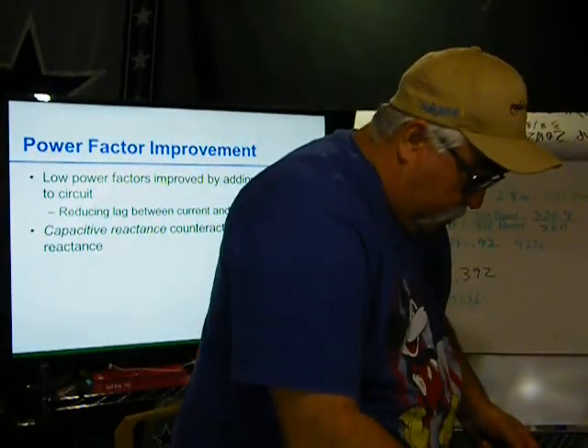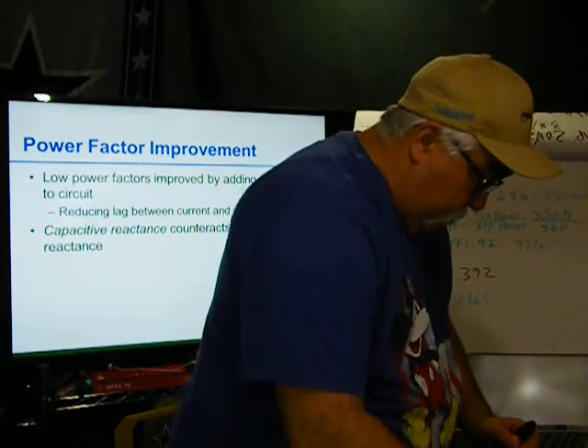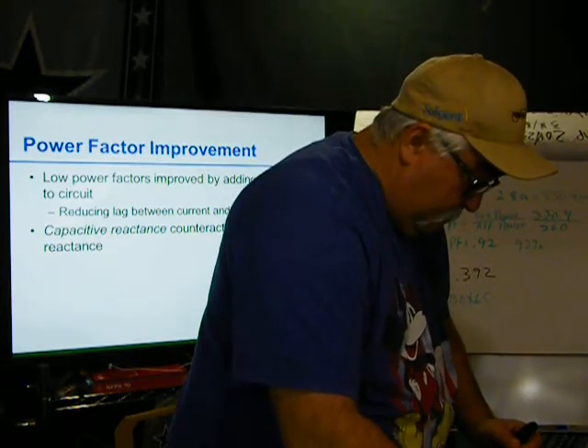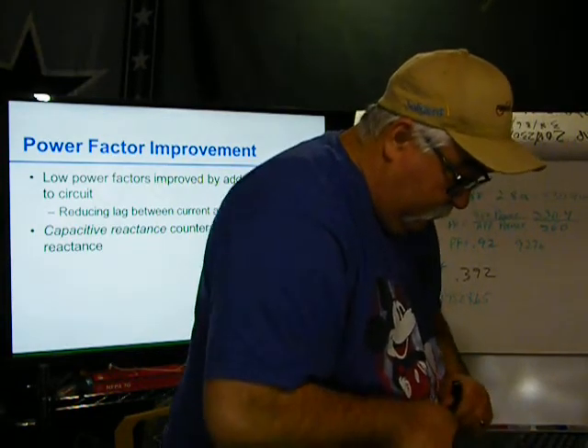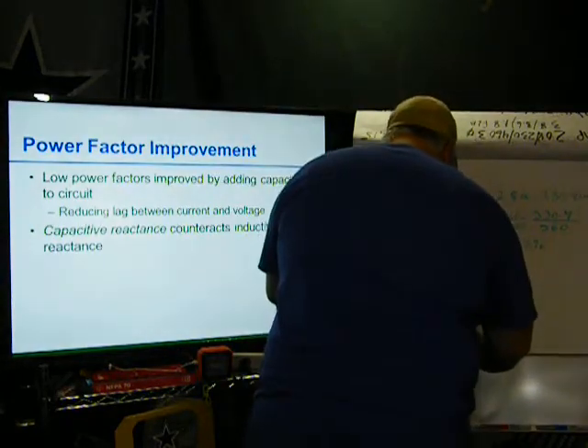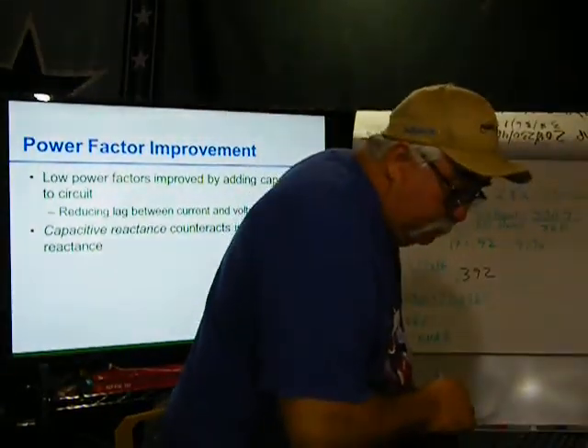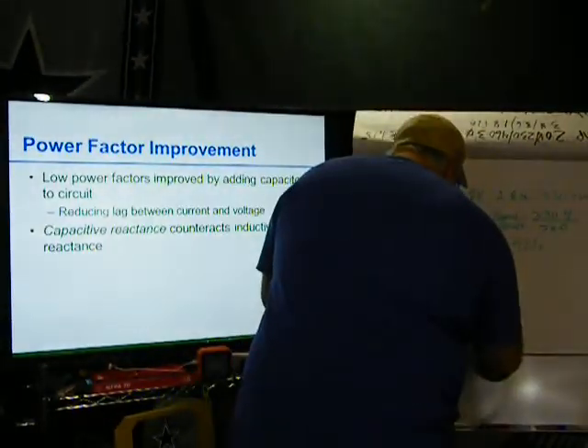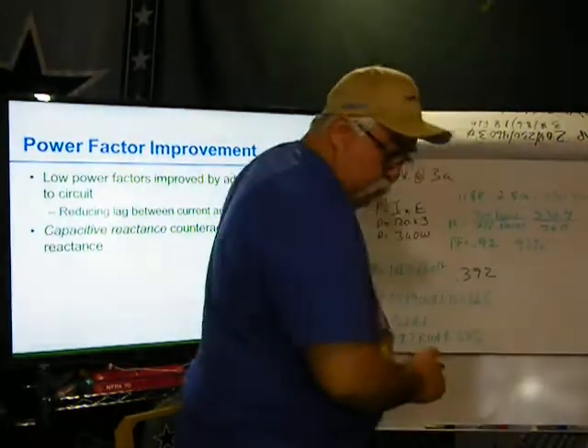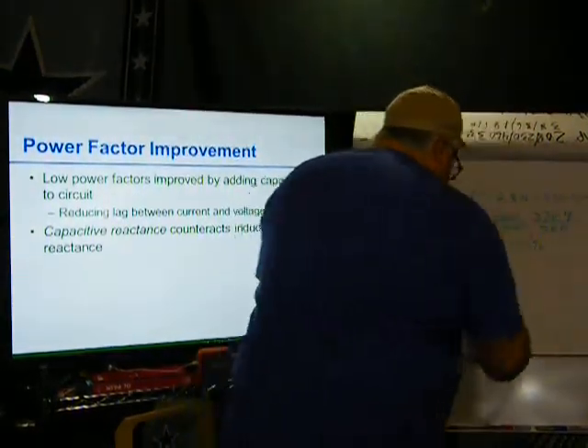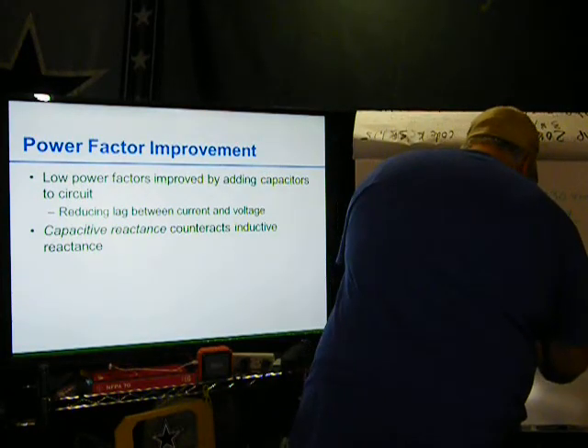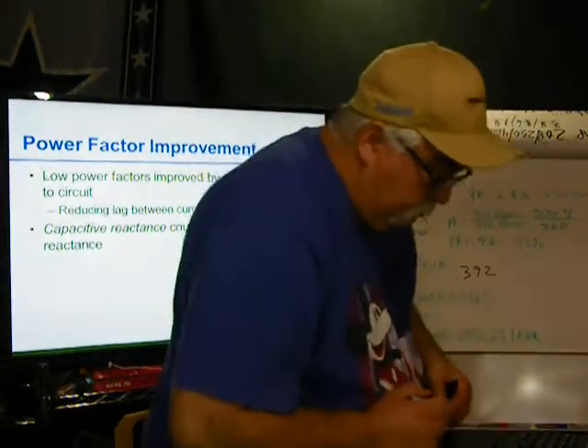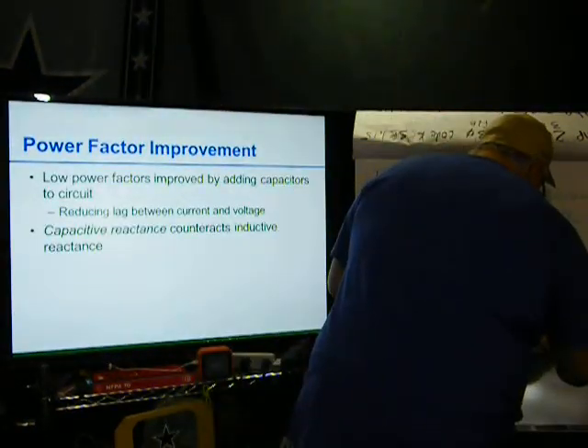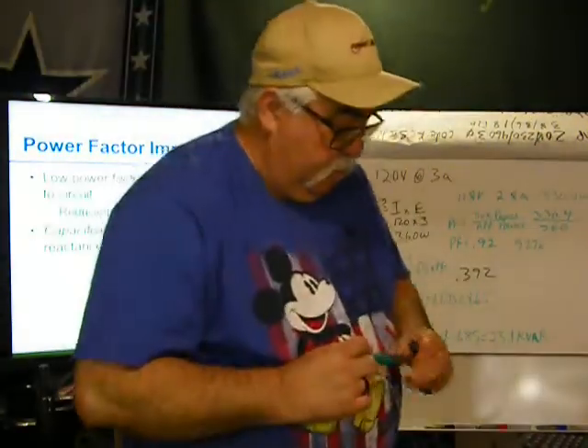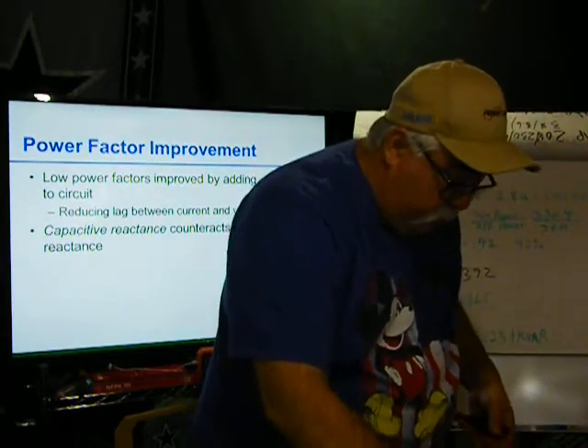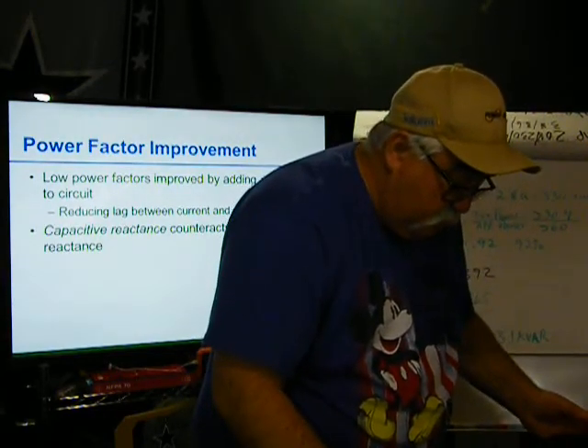It says determine the number from the chart. The multiplier for the intersection at the existing 0.65 power factor and desired 90% power factor is 0.685. So I'm going to multiply this times 33.7, and then I'll do it up above, times 0.685 equals 23.1 kVAR. kVAR, I'm sorry. Kilovolt-amp reactive. So a capacitor rated at 23.1 kVAR can be used to correct the power factor.